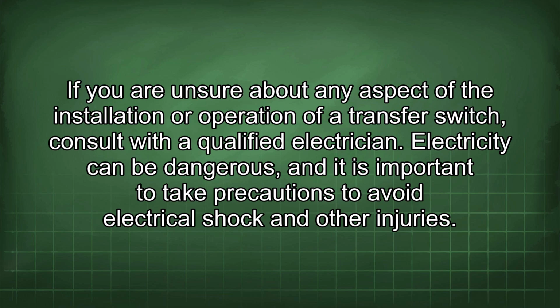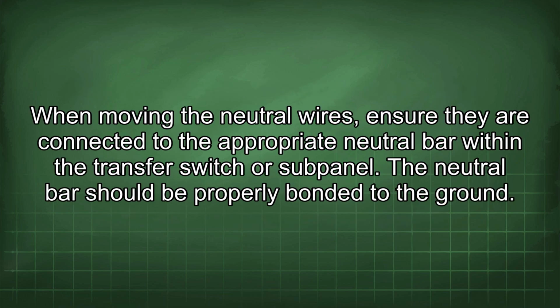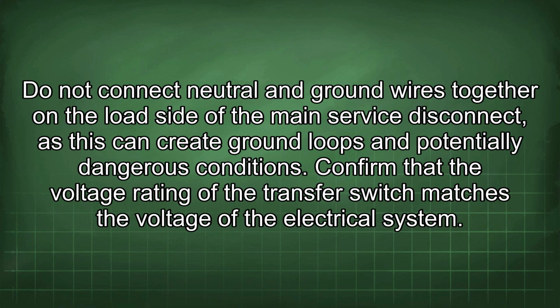Electricity can be dangerous, and it is important to take precautions to avoid electrical shock and other injuries. When moving the neutral wires, ensure they are connected to the appropriate neutral bar within the transfer switch or subpanel. The neutral bar should be properly bonded to the ground. Do not connect neutral and ground wires together on the load side of the main service disconnect, as this can create ground loops and potentially dangerous conditions.